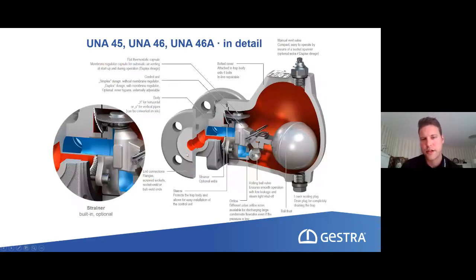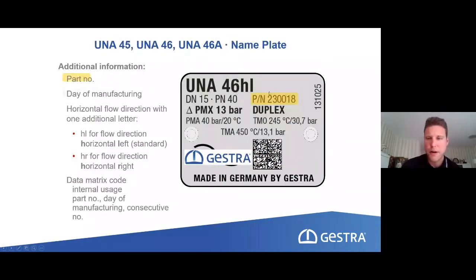So here we have the flange body, and if we have maybe a wall on this side and we cannot install this kind of steam trap here, then we can change the body part to the other side of the steam trap. But you cannot do this on your own, like you could with the flow direction from horizontal to vertical. This is something that has to be ordered because the design looks different here. So the part is a little bit different, but then you also have the possibility to have this body on the other side.